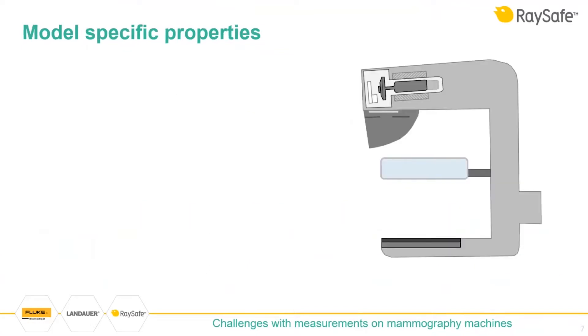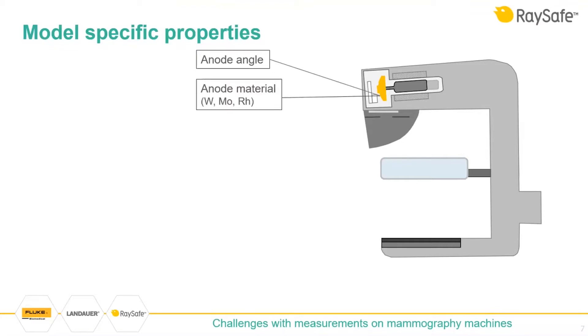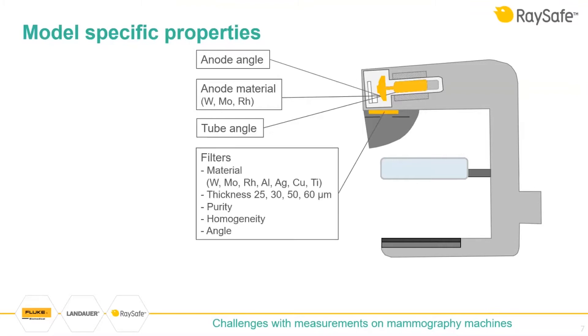There are different types of challenges, and some are model-specific. You have anode angles that can vary between machines, different anode materials and purities, and tubes mounted at different angles. Then we come to filters — the filter can have different materials, different thickness, different purity, and different homogeneity.